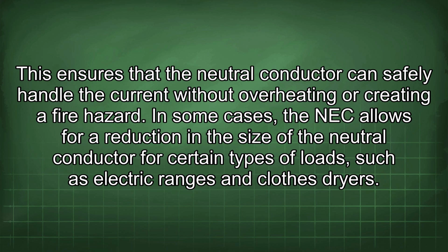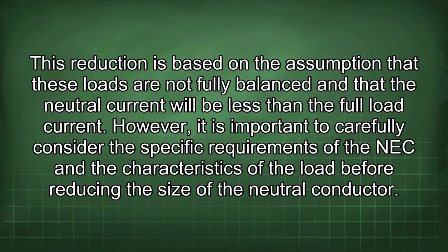In some cases, the NEC allows for a reduction in the size of the neutral conductor for certain types of loads, such as electric ranges and clothes dryers. This reduction is based on the assumption that these loads are not fully balanced and that the neutral current will be less than the full load current. However, it is important to carefully consider the specific requirements of the NEC and the characteristics of the load before reducing the size of the neutral conductor.